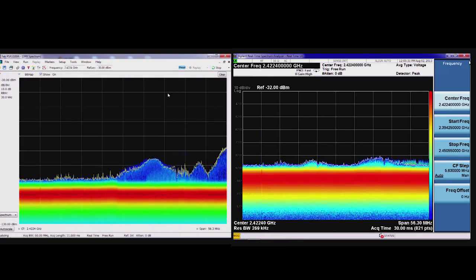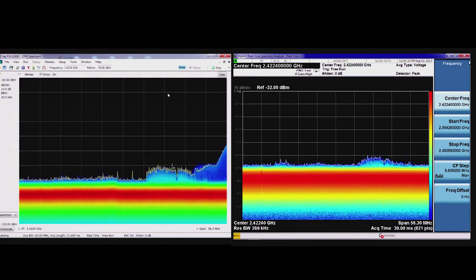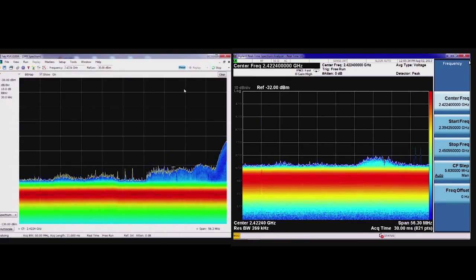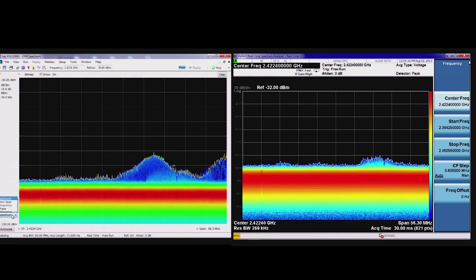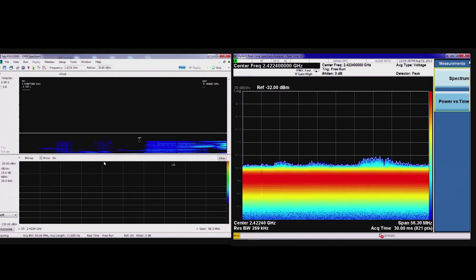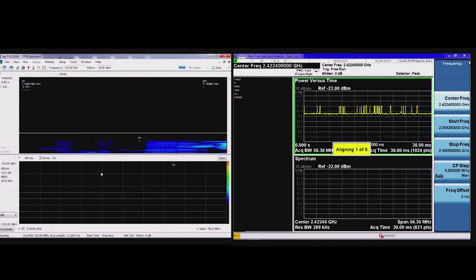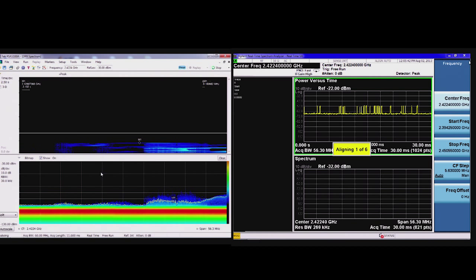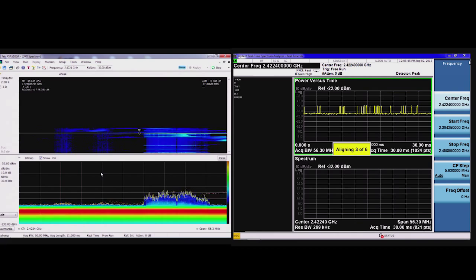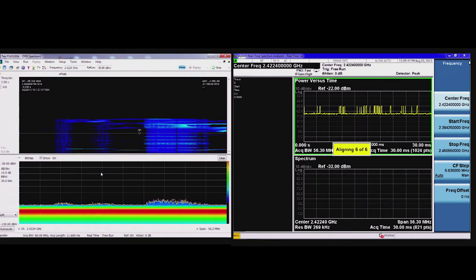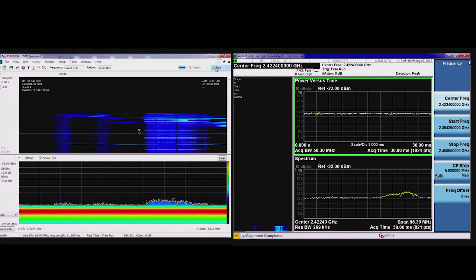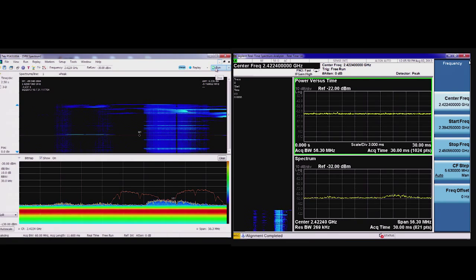So I now have the Agilent PXA set up to the same frequency as the Tektronix RSA. I'm actually seeing different signals because these were recorded at different times. But for the purposes of this discussion, just looking at the spectrogram displays that I have on both instruments. Now, I see the real-time spectrogram on both boxes after the Agilent's finished its alignment.